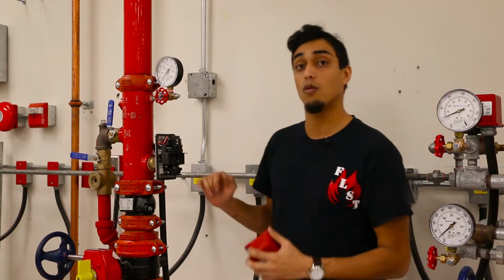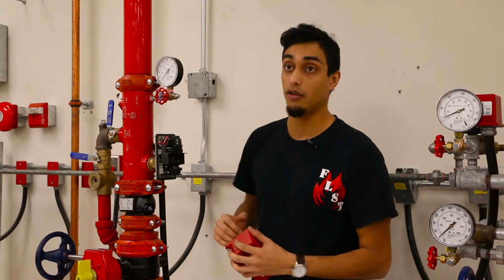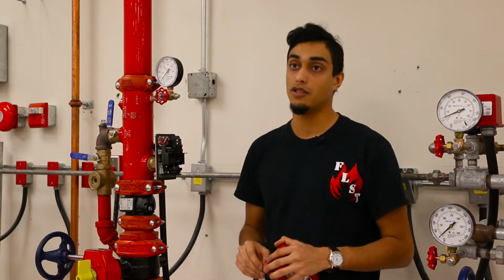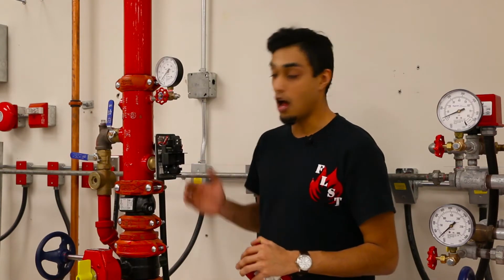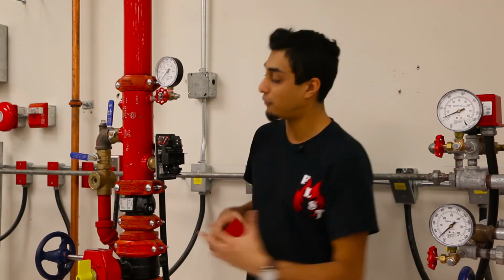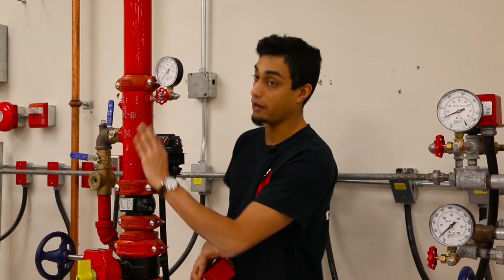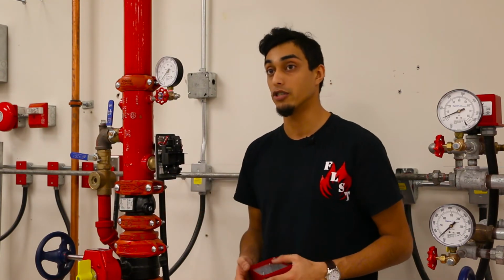What I just did there was an illegal method of testing our device. This is illegal because NFPA 25 explicitly defines the proper testing procedures of a sprinkler system. This includes flowing water to ensure that our paddle does move freely in the event of an emergency.